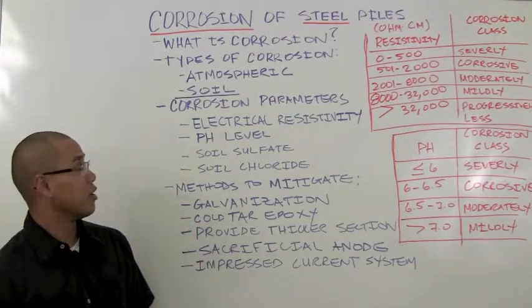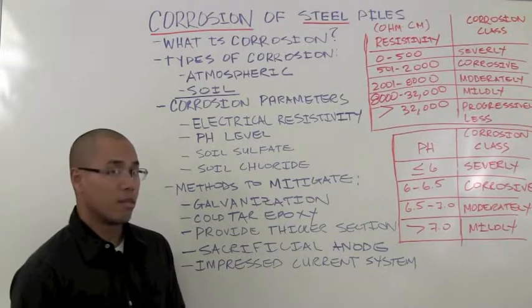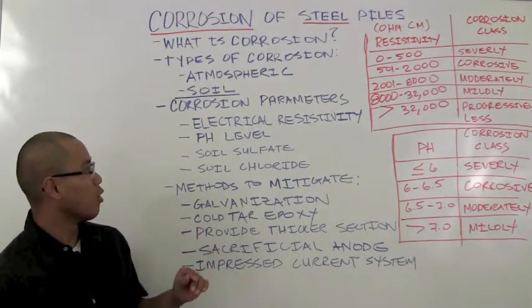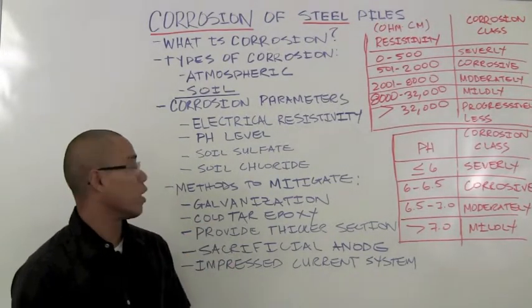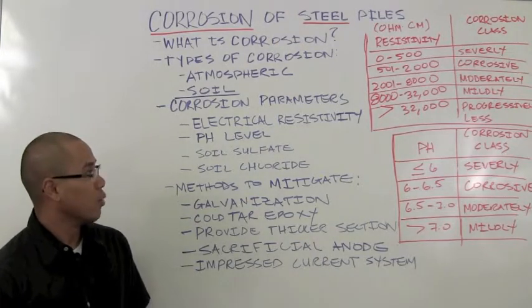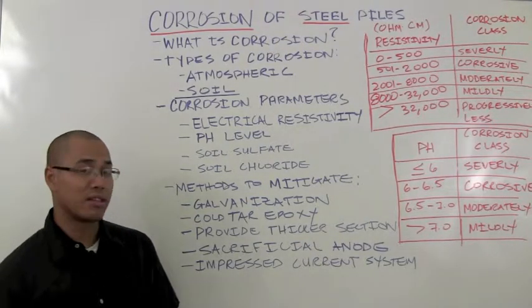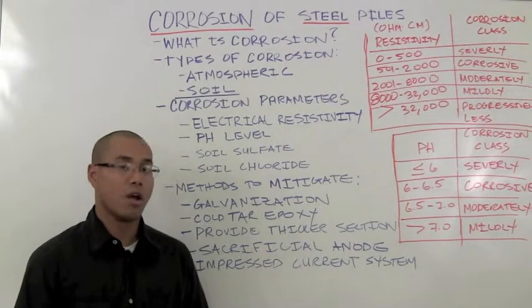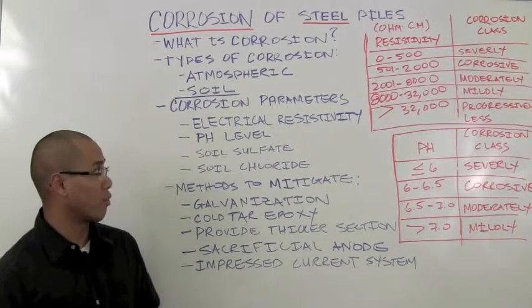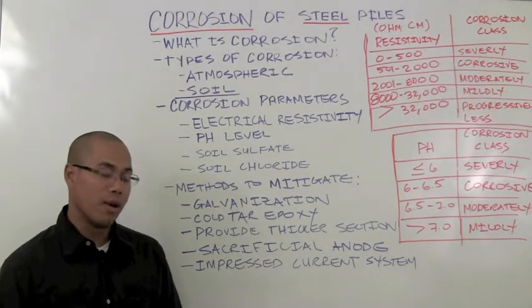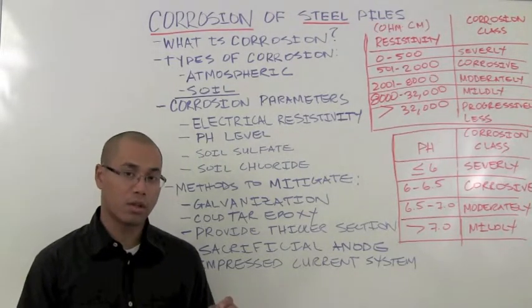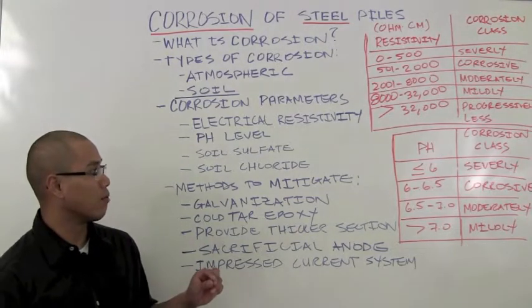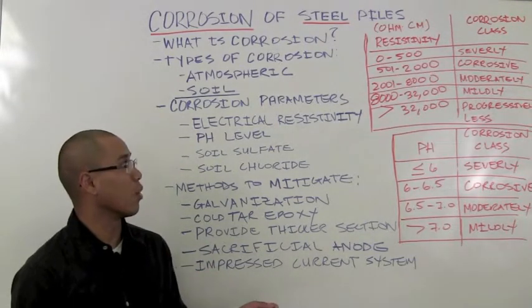If piles are driven into near neutral soils, the major factor that controls corrosion rate is the soil electrical resistivity, which is defined as the soil's resistance to electrical current across a cubic meter of earth. This is typically driven by soil chemical properties and also the amount of moisture within the soil.